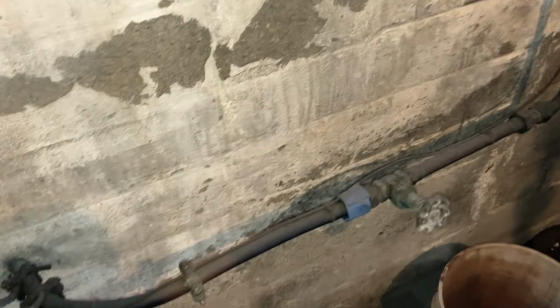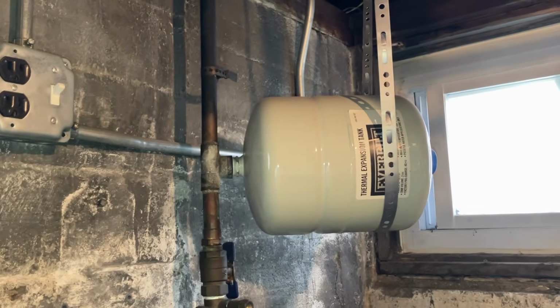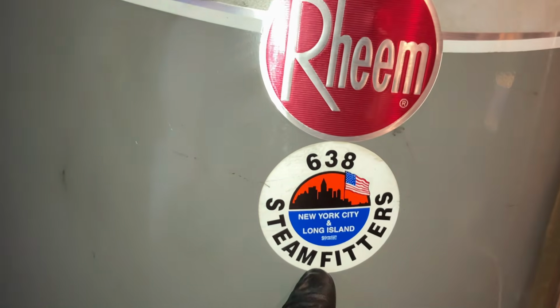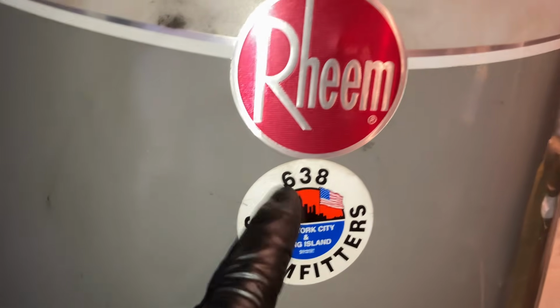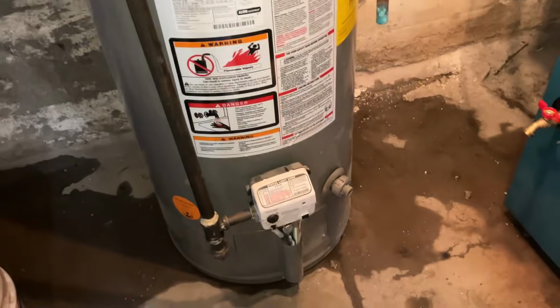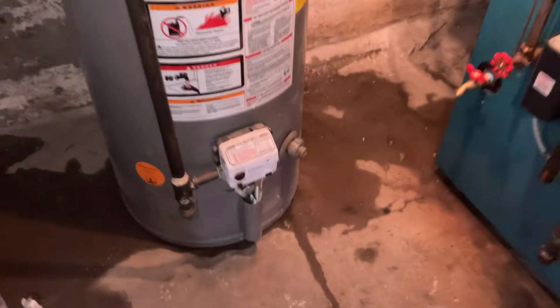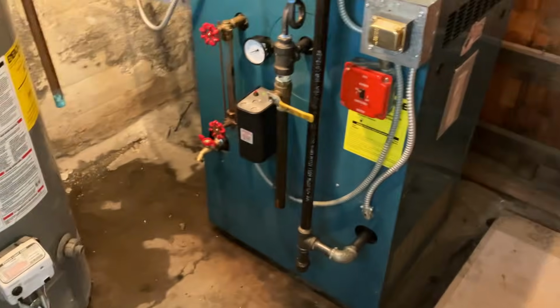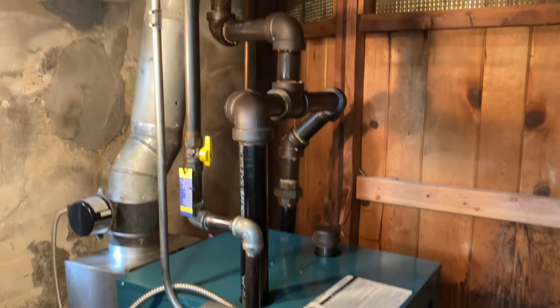Valve tags in the boiler water supply, gas for the boiler, gas for the water heater supply, main water valve. Water meters at the curb, in a curb box. Expansion tank installed improperly, but not here for that. Maybe blame the local steam fitter shopping at Home Depot. You get that Home Depot plastic drain valve. Nicey nice. This is a beautiful job.